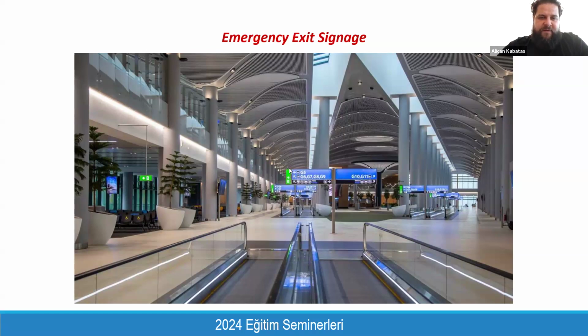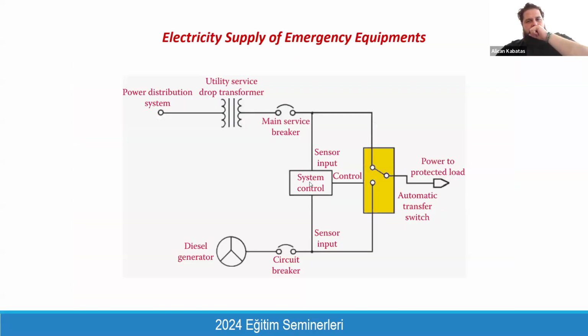You can understand that this is an emergency exit signage, and if you follow these green ones, you can reach to the exit access. But the other ones are showing the restrooms, the restaurants, or the gates. And also the emergency equipment should be fed by both main electricity and also the diesel generator. And that's why it is important to find a place for automatic transfer switch when you are designing a room for fire pumps, for pressurization fans, or for smoke extraction plants.